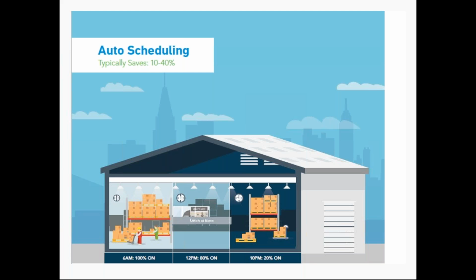This is a great way to automate energy savings by controlling the desired light levels throughout the day or night without wasting electricity. Looking at the example on the board: when everybody comes into work at 6 a.m., 100% on, we have a nice bright area. But when lunchtime rolls around and you've got different shifts and different departments going to lunch, you can dial it back, maybe to 80%, maybe to 90%, to really capture some savings there. And then at nighttime, you could dial it back down to 20% or have some of your other strategies take over to regulate the lighting.